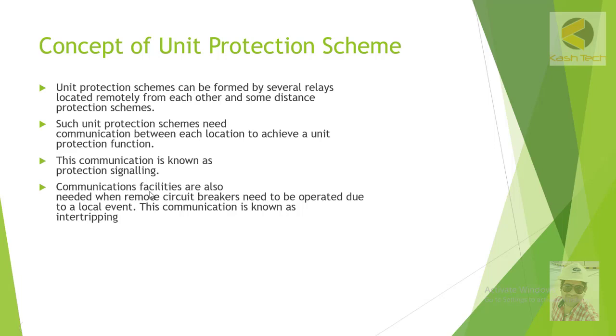In a unit protection scheme, when there is a fault on a unit — for example a transformer or a line — it trips the feeding sources simultaneously. In a graded protection scheme, tripping is done in grades: for example, if you have a 400V incomer breaker and an outgoing breaker, a fault on the outgoing feeder will first trip the outgoing breaker, and only if that is unsuccessful will the incomer trip. This is graded protection.